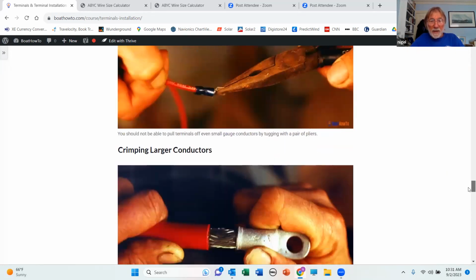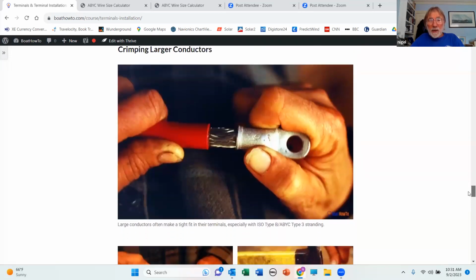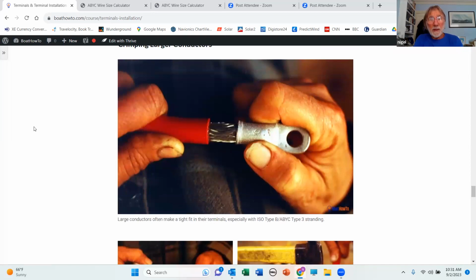And then as they tug on it nice and hard, you're going to find with these really large conductors that very often they're very finely stranded. And for a given amount of copper cross-sectional area of the conductor, the more the strands, the fatter the conductor gets to be because of all the air spaces between the strands. So very often you'll find it's a real struggle to get the conductor into the terminal, but you need to make the effort and try to minimize the number of strands that end up splayed out and don't end up going into the terminal. You want a decent tight fit in there, which brings me to another question.